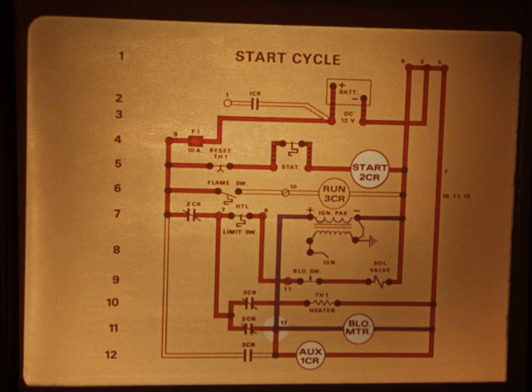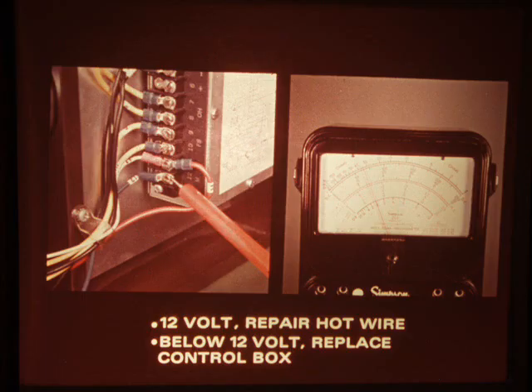The ignition pack is fed from terminal 12 on the control box, so check for voltage there with the furnace turned on. Incidentally, to turn on the furnace while it's on the bench, just short together the two thermostat leads. If there's 12 volts available at terminal 12, repair the red or hot wire to the ignition pack. If there isn't 12 volts, replace the control box. And that covers the condition where the burner doesn't light, but the blower runs.